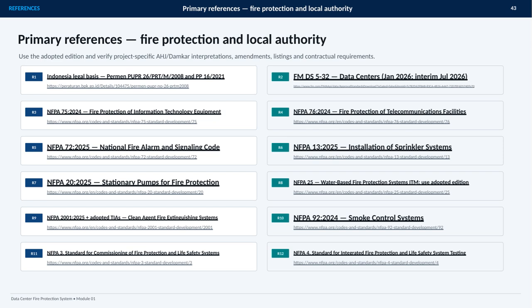26/PRT/M/2008 and PP 16/2021. FMDS 5-32 addresses data centers, with the additions and interim timing identified on the slide. The NFPA references then cover the major technical disciplines. NFPA 75 for information technology equipment, NFPA 76 for telecommunications facilities, and NFPA 72 for fire alarm and signaling. NFPA 13 addresses sprinkler installation, NFPA 20 covers stationary fire pumps, and NFPA 25 provides inspection, testing, and maintenance requirements for water-based systems. For specialized protection, NFPA 2001 covers clean agent systems, while NFPA 92 addresses smoke control.